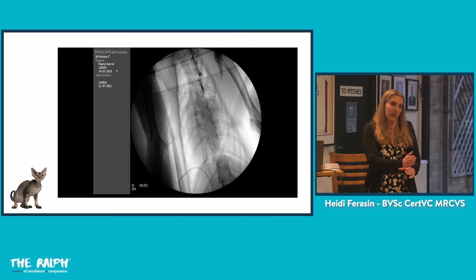So for the vast majority of the cases, we use what they call an inflation device, which has a pressure gauge on it as well. It's a literal manual screw that you push to a certain point and then you start screwing for that final inflation, and you can see the pressure gauge. We only go up to the pre-agreed pressure based on the manufacturer of the balloon, so we know what the bursting pressure is. Once we've reached that pressure, you hold it for a few seconds, and then it's a rapid deflation with that device. So you do lose output for, what would you say, 10, 15 seconds? Something like that.